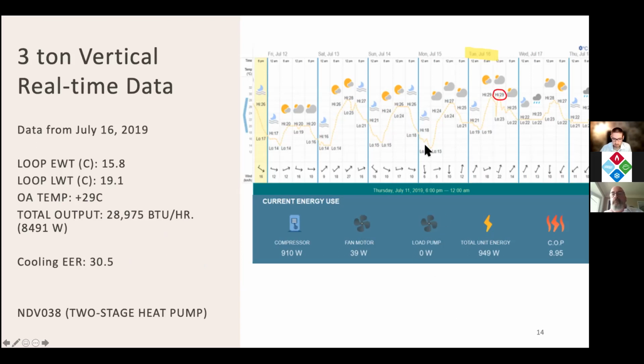We're going to talk a little bit more about those numbers later on in the presentation when we look at air source heat pumps comparatively. But these have major impacts on at-scale adoption on electricity grids, and that's one of the major benefits of ground source heat pump adoption. It's also interesting to note that we have to think about these ground loops as thermal batteries. They're seasonal storage. We're rejecting heat to these ground loops in the summertime, and much of that heat is being stored and then reused in the winter heating season. So it's an annual cycle of heating and cooling.